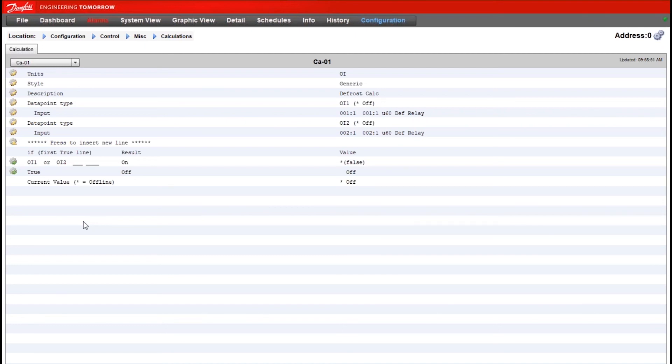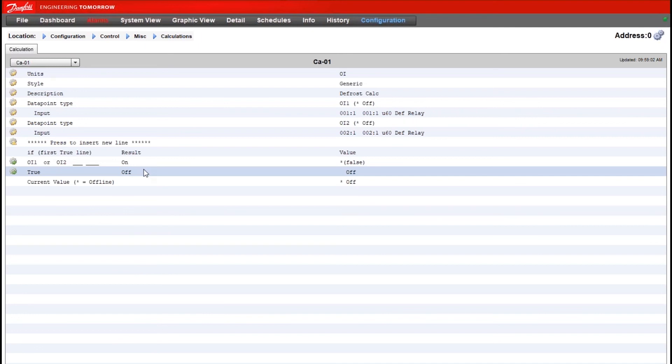And then from here just keep in mind that if you want to use this calculation for say a miscellaneous relay, you would then have to go to that miscellaneous relay section and assign the calculation number as your control input for that relay so that it would apply to the logic of that relay.